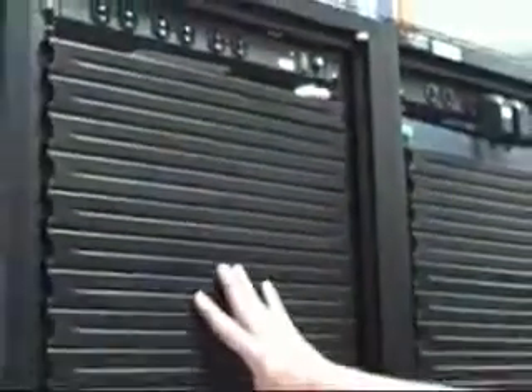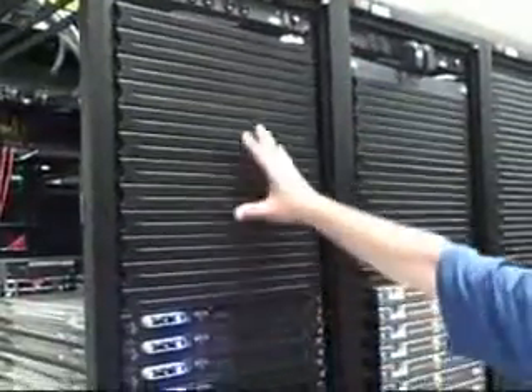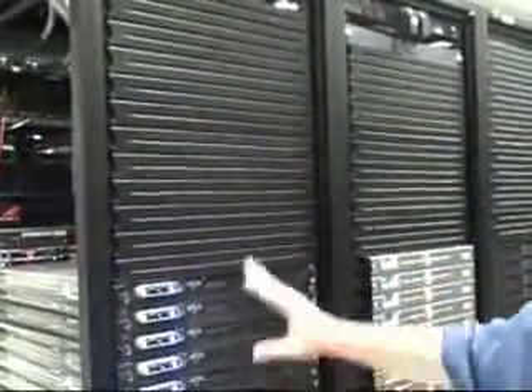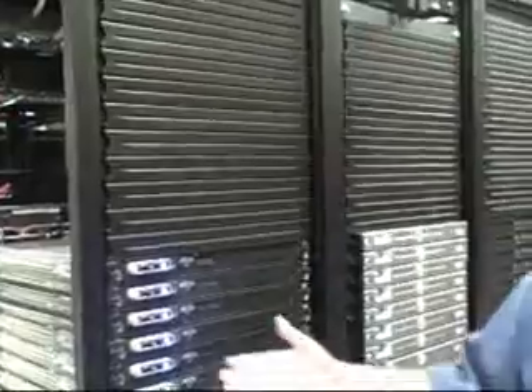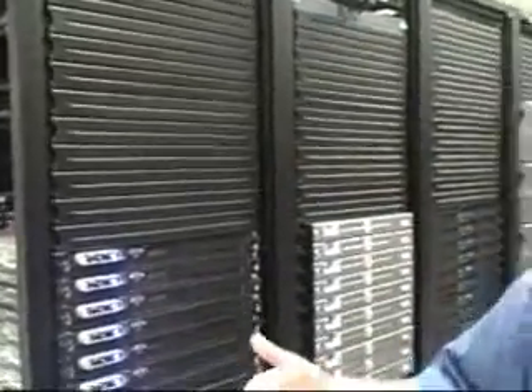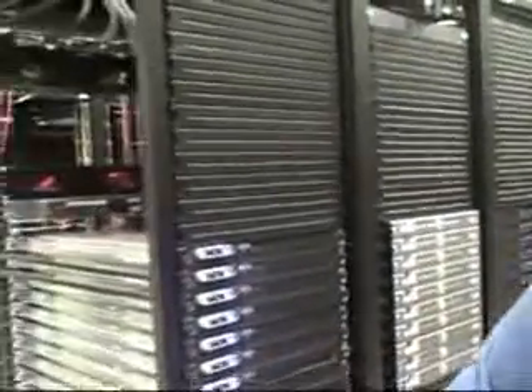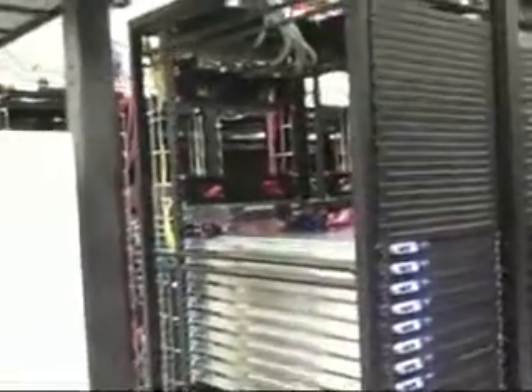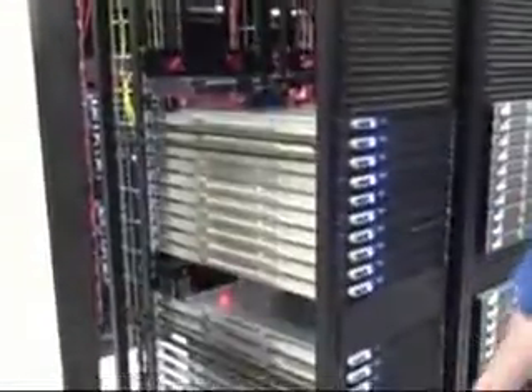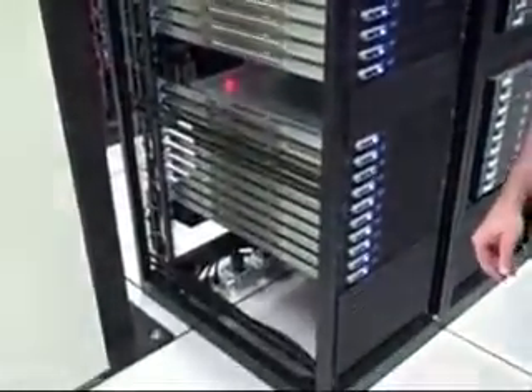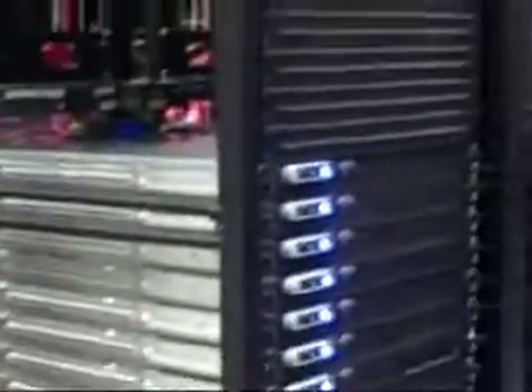Obviously we've got blank plates in place where we don't have servers in the cabinets to help stop the mixture of the hot and cold air. Another thing we've employed is where we bring the power into the cabinets at the bottom. Rather than having the power outlets under the floor and running the cords all through the floor for a grommet, we actually keep that above the floor to completely eliminate air coming through the grommets from the raised floor in an area where we don't want it.